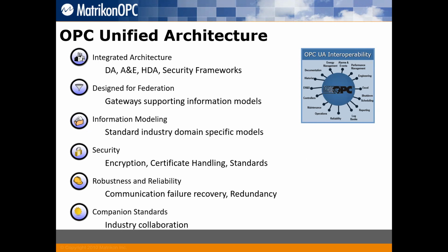The main difference about the OPC UA is that it created its own communication stack. It didn't use an existing technology like COM and DCOM. That's why we say that the OPC UA is not attached to Windows, because it does not need COM and DCOM. This is the reason why we can see a PLC, a microcontroller or a sensor with an OPC UA server embedded. Of course, we don't have Windows in a PLC. It's because the OPC UA technology does not use COM and DCOM anymore.